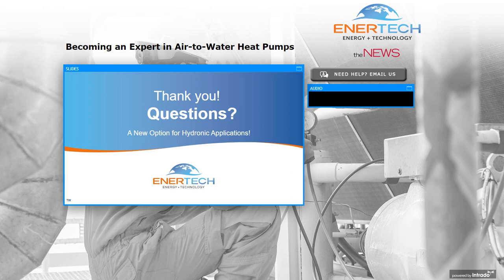If they have an existing boiler, they may want to continue to use that boiler as backup. And if it's forced air, then we could certainly replace the furnace or heat pump with a hydronic air handler, and we could stay with the ductwork. If it happens to not have ductwork, we can couple it with ductless indoor units and use chilled water and hot water there. So it's really ideal for retrofits because of the flexibility with the hydronic applications.